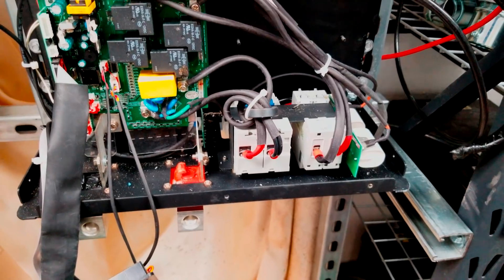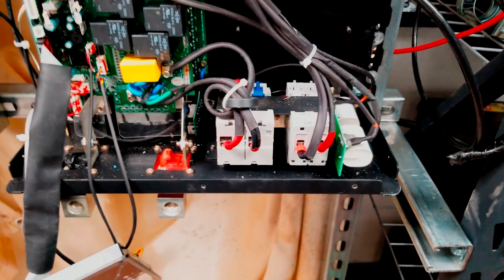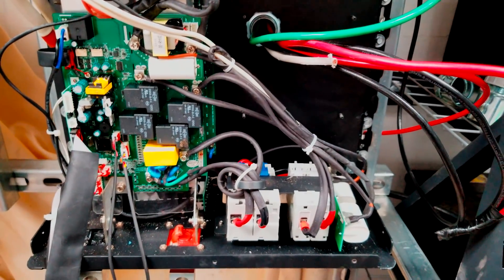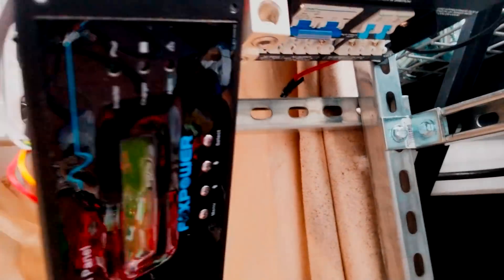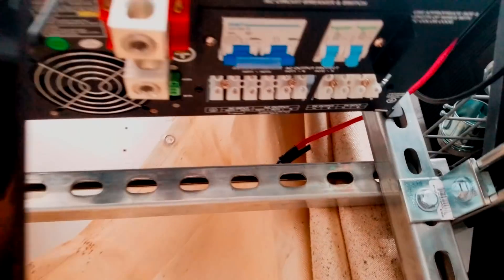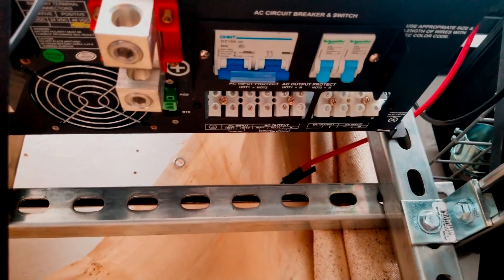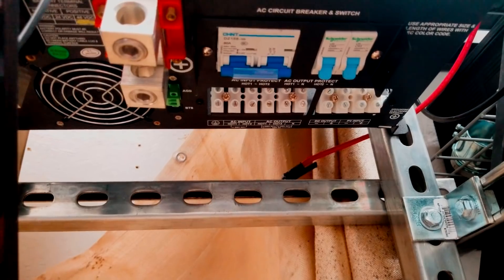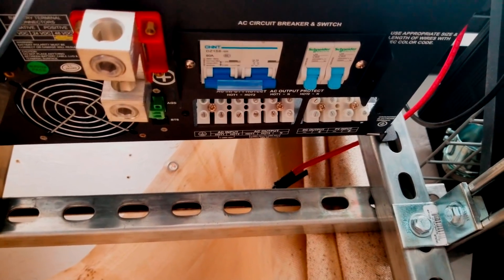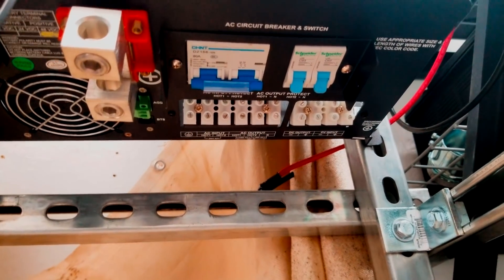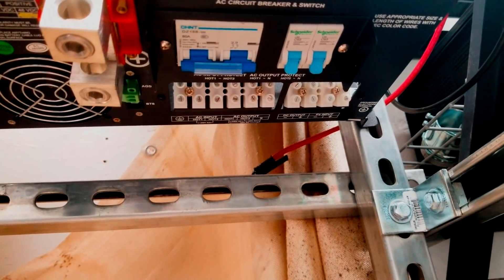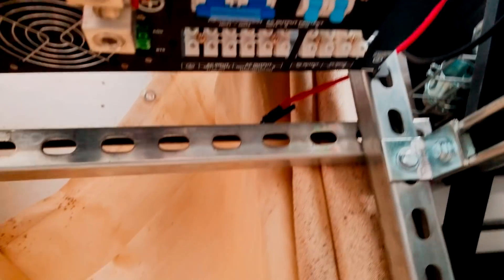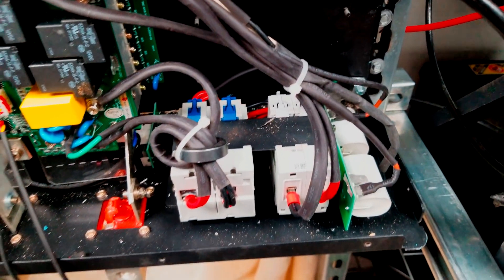Because as you can see, there's a couple of small wires. I don't feel comfortable having those small wires taking the full capacity of the system. So I'm just gonna go straight on to the circuit breakers. It's a much stronger connection. There's less splices, and it'll be better. Now the manufacturer doesn't really recommend opening the unit. They actually have a warning sticker on the side that there's dangerous voltages. But I don't feel comfortable having exposed, not in conduit, coming off these terminals. That's the only downside with these inverters is they don't have very good termination.